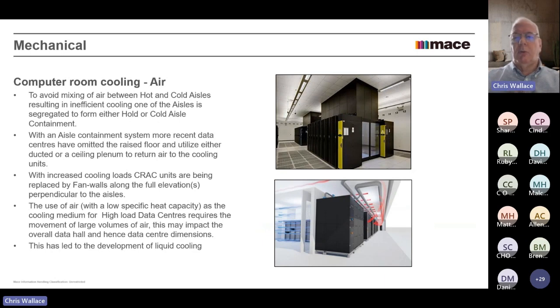When people started getting really sensible about cooling, what used to happen is that some of the cold air that went into the cold aisle went over the back of the cabinet, around the side of the cabinet, and mixed into the hot air in the hot aisle. So the air that was brought back to the CRAC unit was cooler than it ideally should have been, because you had some areas where the equipment was doing a lot of work, and this would have been diluted by spillage of cold air. So you weren't getting an accurate balance between the load that you needed and what the cooling units were doing.